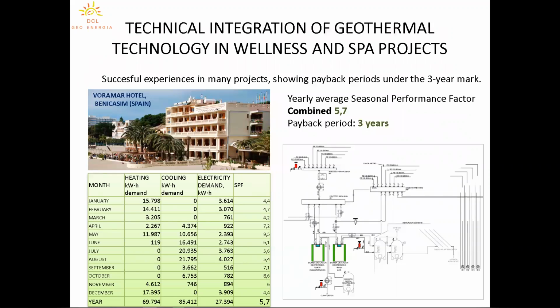The air always has some salt and chlorides, which are quite aggressive to metallic parts. So, as you know, external units of chillers tend to rust and experience salt deposits and so on, and have to be replaced every 8 or 10 years. We have been working on and maintaining geothermal systems that have been running for 30 years with no further issues, unlike the usual maintenance needed for chillers.